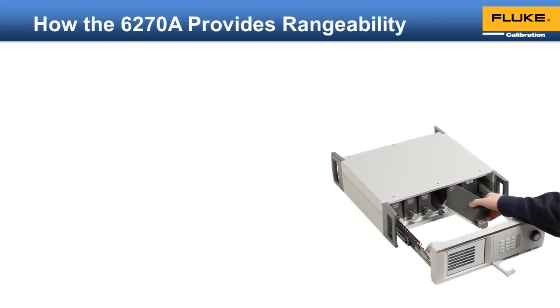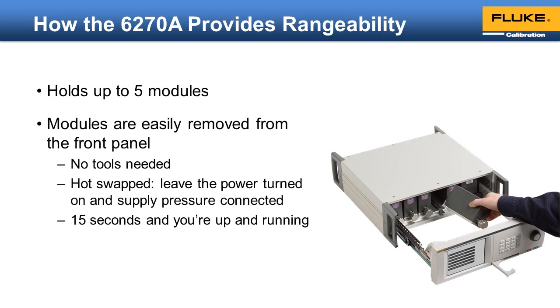How does the 6270A provide rangeability? First, you can install up to 5 measurement modules at any one time. These modules can be easily removed through the front panel. No pressure lines need to be disconnected from the unit, and the power can remain on. So, even if the 6270A is installed in a cabinet where you cannot get to the back of the unit, you can still easily switch out the modules. In 15 seconds, with absolutely no tools, you can completely rearrange the instrument.